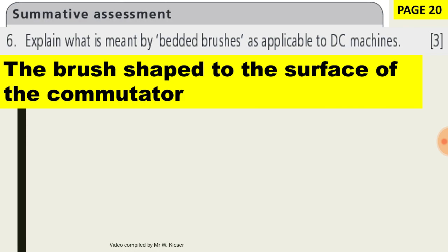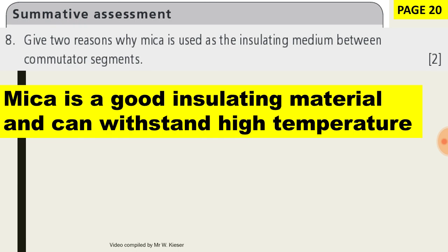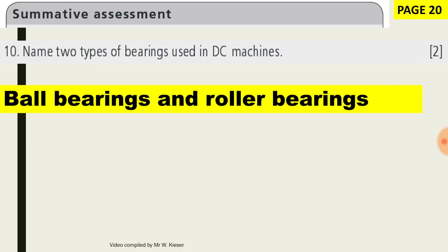The term 'bedded' or 'bedding of brushes' means shaping the surface of the brush to the commutator. Two important properties of carbon brushes: they are hard-wearing and can withstand high temperature, they are cheap, and carbon dust acts as a lubricant. Mica is used as an insulating medium between commutator segments because it is a good insulating material and can withstand high temperature. The commutator is made up of hard drawn wedge-shaped copper segments. We get two types of bearings: ball bearings and roller bearings.